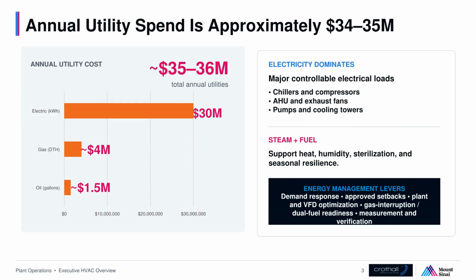Before we discuss equipment, we need to understand the scale of the energy involved. Annual utility spending: electricity is the largest portion because chillers, compressors, fans, pumps, and cooling towers are major loads. Energy management therefore includes both operating savings and outside funding. Utility incentives may offset part of the cost of qualifying chiller upgrades and other verified efficiency projects. We still need sound engineering, commissioning, and measurement and verification. Demand response is different. During summer grid events, we switch load from utility power to generator power, and reduce approved non-critical electrical load by utilizing setbacks while protecting patient care.